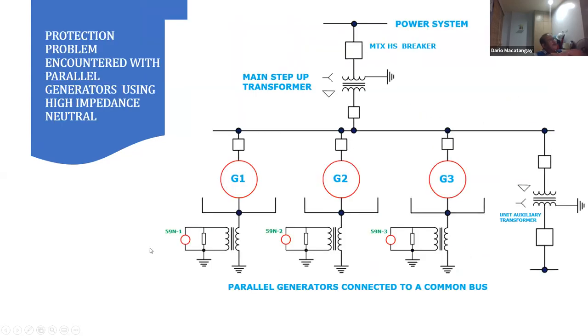All right. Now, the problem here is when you're using a 59N in parallel generators. The problem associated with this is that if you have a ground fault, let's say on G3, the same voltage will appear on the secondaries of this neutral grounding transformer. If that happens, all of them will trip. So you don't have selectivity, that's the problem here. That's why this is typically used in industrial plants with parallel generators, but it's a little bit more involved to actually design the relay because of this problem.